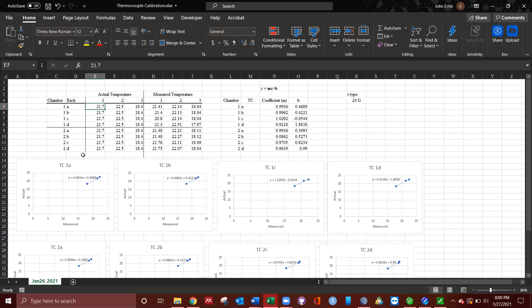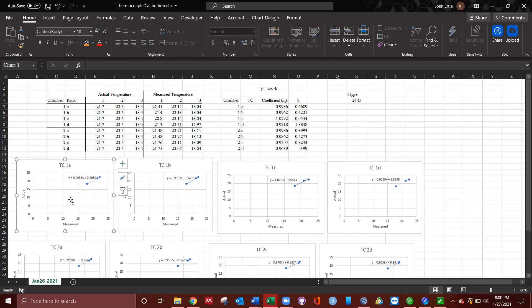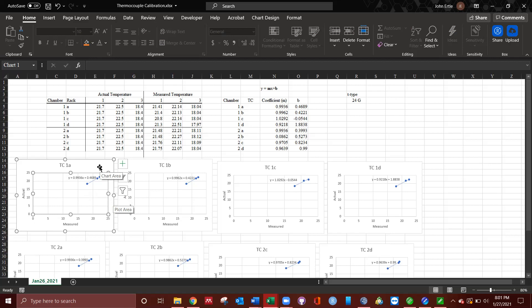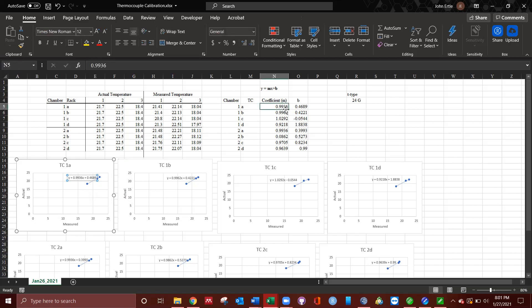So what I've done is I have measured the temperature in the basin at the same time that I was measuring the thermocouple temperature. By connecting to the data logger and reading off the live values, I'm able to do this. I created a series of charts with the thermocouple measurements on the x-axis and the actual measurements on the y-axis. I did this because I want to create a y equals mx plus b equation that I can use in my program to make sure that the thermocouples are accurate. In this case, y equals mx plus b, and then this value is transferred over here. I have the coefficient m, I have the offset b. I'll plug that into a program.